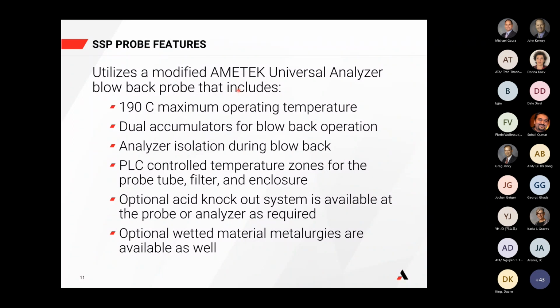So the maximum operating temperature is 190 degrees C. This is limited by the T3 rating of the certification, the Div 2 certification. Again, we have dual accumulators for blowback operation. One is dedicated towards the probe filter. One is dedicated towards the probe itself. We do isolate the analyzer during the blowback function. We use a PLC to control the temperature zones for the probe tube, filter, and enclosure. And all three of those zones have the ability to go up to 190 degrees Celsius. There is an optional acid knockout system for higher dew points, things that are higher than 190 degrees C, that can be used.